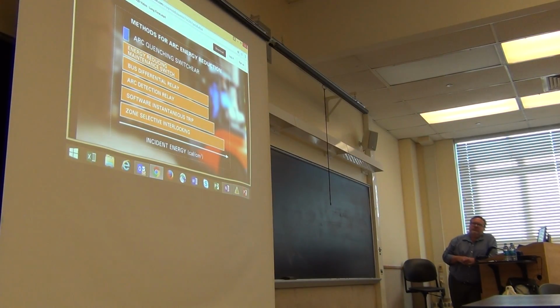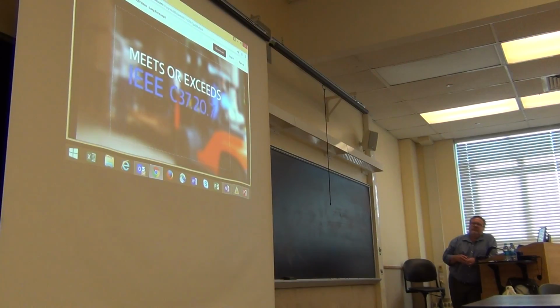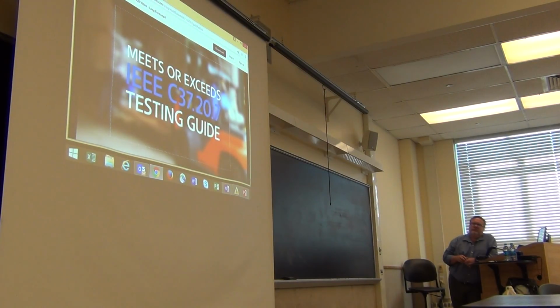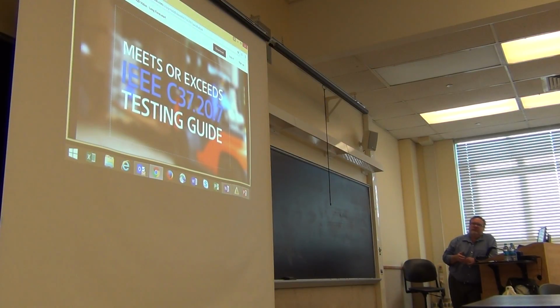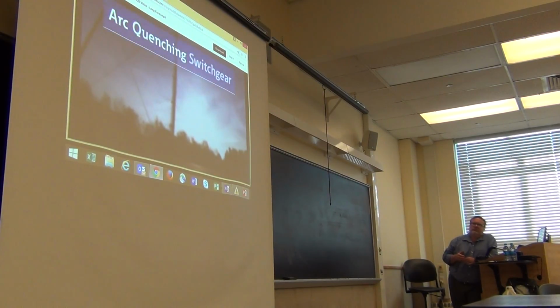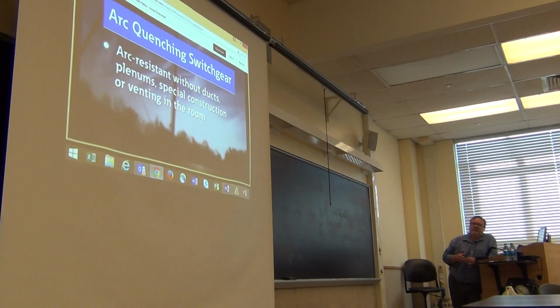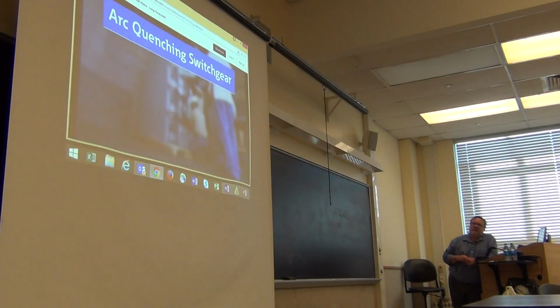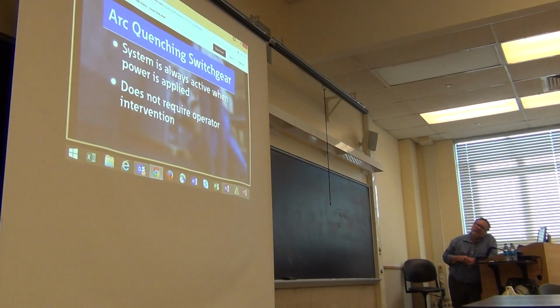The result is dramatically reduced incident energy levels, which minimize or completely eliminate damage to the switchgear and yield superior personnel protection. Protection that meets or exceeds the IEEE C37.20.7 guide for testing metal enclosed switchgear for internal arcing faults. Arc quenching switchgear provides arc resistance without the need for ducts, plenums, special construction, or venting inside the room. And it maintains its arc-resistant rating even with breaker doors open and breakers removed. The system is always active when power is applied. It does not require any operator intervention when properly maintained.